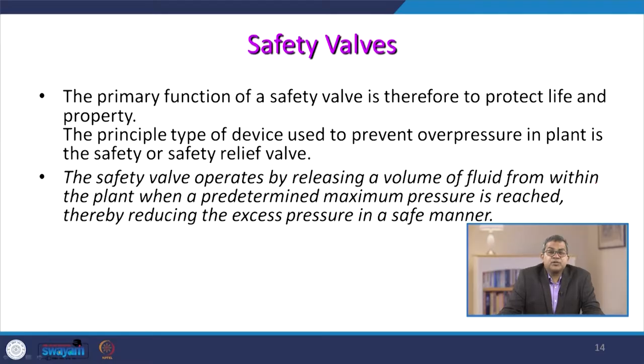Now let us talk about safety valves in detail. The primary function of a safety valve is to protect life and property — similar to the example of a domestic pressure cooker, which is a pressure vessel equipped with two different types of safety devices. The principal type of device used to prevent overpressure in plant is the safety or safety relief valve. The safety valve operates by releasing a volume of fluid from within the plant when a predetermined maximum pressure is reached, thereby reducing the excess pressure in a safe manner. Recall that a boiler has three different pressure ratings: working pressure, bursting pressure, and hydraulic pressure.